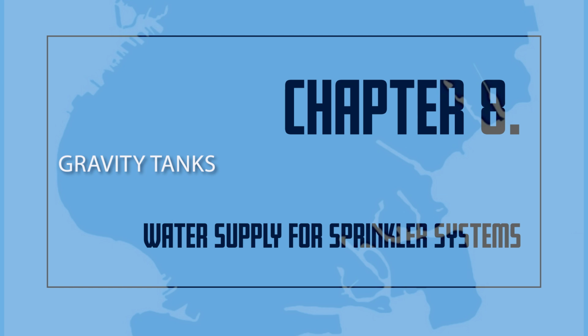Gravity tanks. Gravity tanks of adequate capacity and elevation make a good primary supply and may be acceptable as a single supply. A gravity tank may be located on the top of a building or on a tall tower. The water in the tank is distributed throughout the sprinkler system because of the pull of gravity.